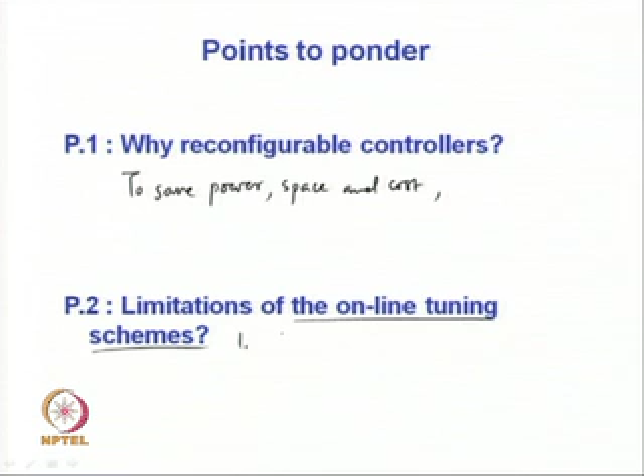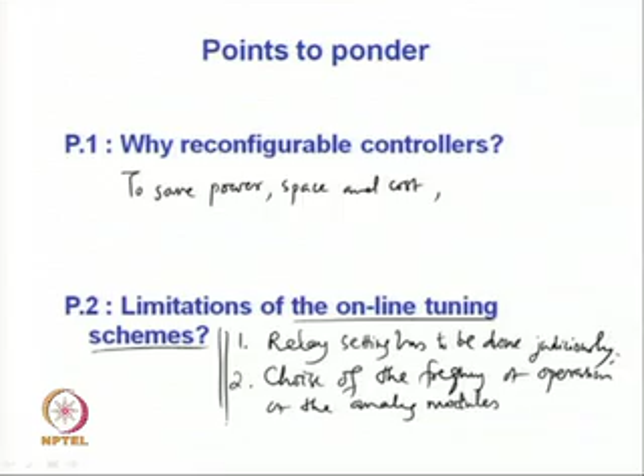Are there any limitations of the online tuning schemes? Yes, one has to be very careful when you are doing real time experiments. Particularly, you need to carefully set the relay parameter. So, relay setting has to be done accurately, or I would say judiciously. Secondly, the choice of Fc, choice of the frequency of operation of the analog modules. These are the two things you must take care of while designing a FPGA based reconfigurable PID controller. Thanks.